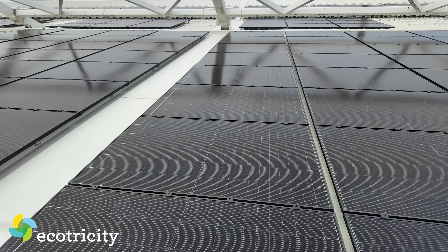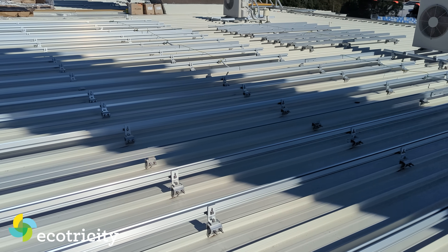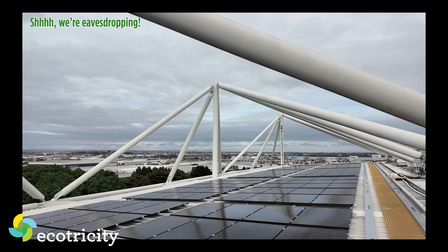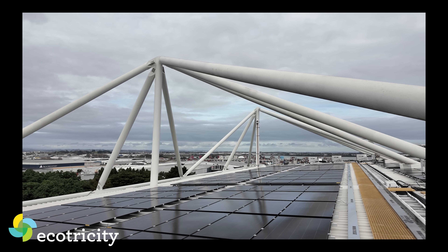I've rocked on up and it all looks easy — was it a piece of cake? No. Engineering caught us a bit, but in the end we just had to add more rails. From the engineering side, we had to quadruple the amount of rails and clamps on this roof to make it sound. Last time I was here there was nothing on the roof — just a helicopter. We also had to wait for more clamps to arrive. Originally it was 10,000 clamps over the project, which went up to about 23,000 clamps.